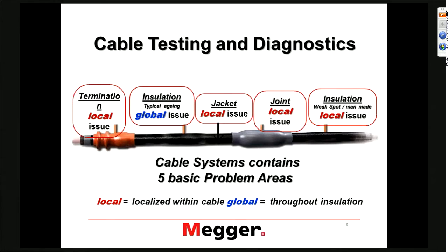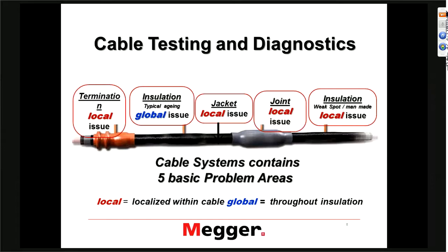The third issue we might encounter is the jacket. Basically all power cables today are jacketed cables, and the jacket offers some protection against mainly water or moisture ingress. So if the jacket is damaged, this can lead to moisture ingress and eventually to water treeing and failure of the cable. The jacket is also something we want to be looking at, but it is typically a local issue.